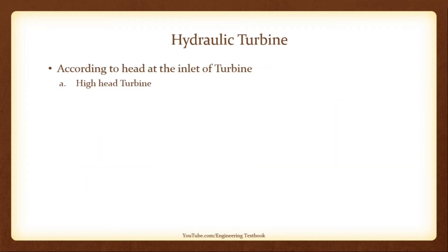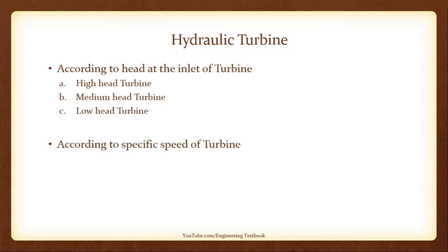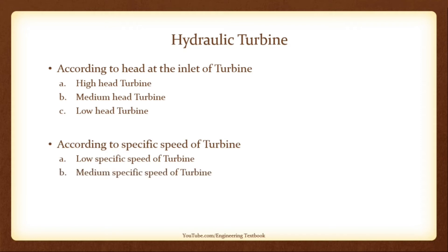According to head at inlet: A high head turbine has a net head ranging from 150 to 2000 meters or more, and requires a small quantity of water. A medium head turbine has a net head from 30 to 150 meters and requires a moderate quantity of water. A low head turbine has a net head less than 30 meters and requires a large quantity of water. According to specific speed: low specific speed turbines have specific speed less than 50; medium specific speed turbines range from 50 to 250; high specific speed turbines have specific speed more than 250.